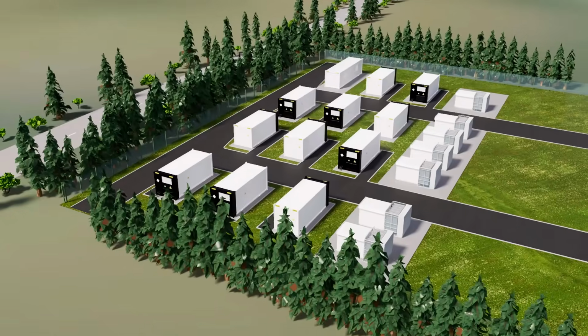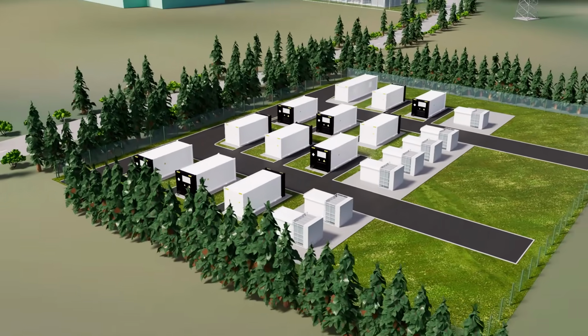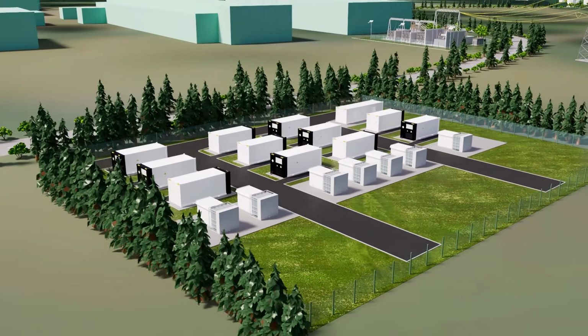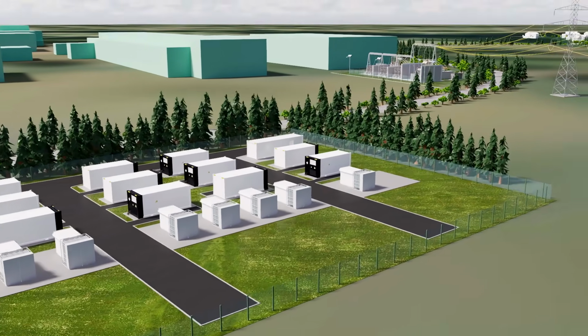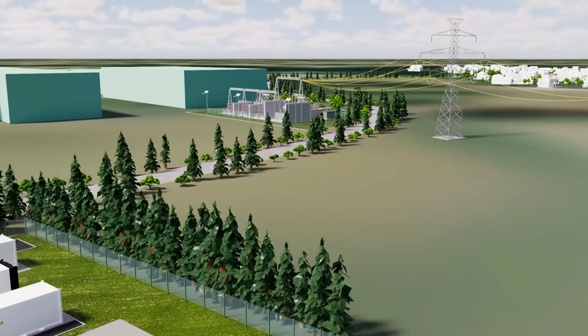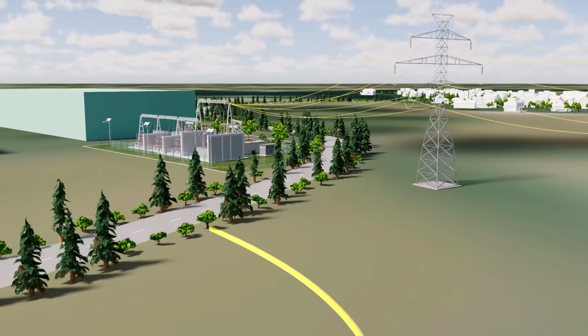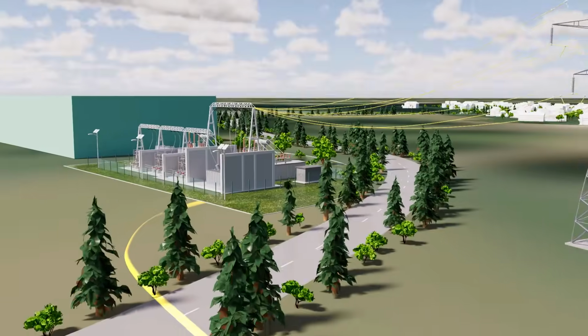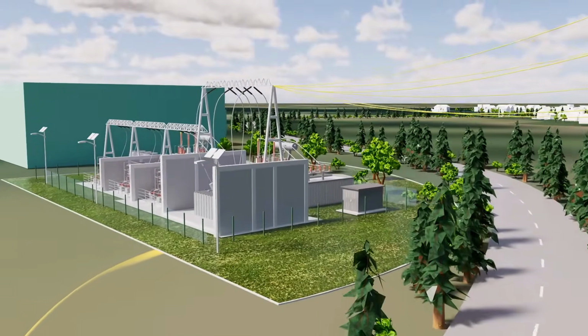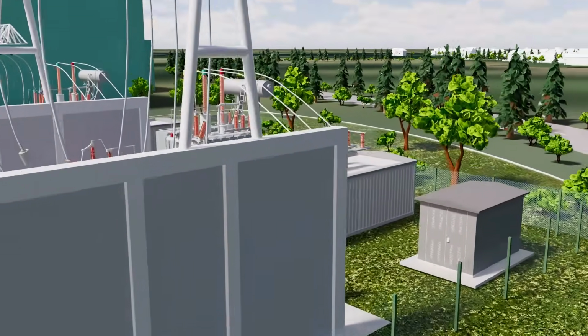Applying a so-called black start, the batteries feed power into the local medium voltage grid. At the same time, this grid is disconnected from the rest of Germany's power grid at a nearby substation.